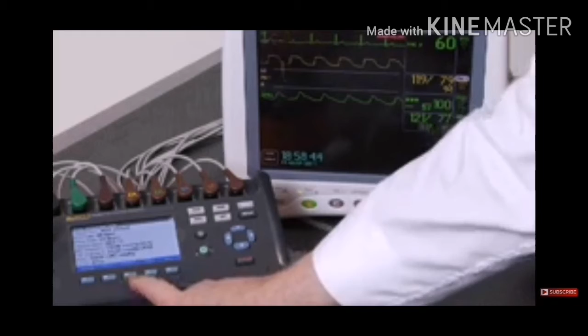It's gotten 119 over 79 with a mean of 93 for invasive blood pressure. And the cuff is making its measurement now for the NIBP reading. O2 sat is 100%. There we go, 121 over 77 versus 120 over 80, pretty good. We'll go to hypotensive now and start another cuff measurement.